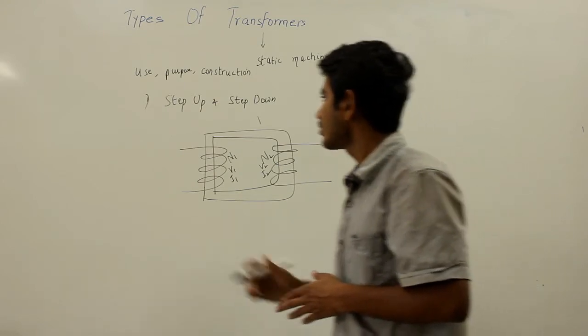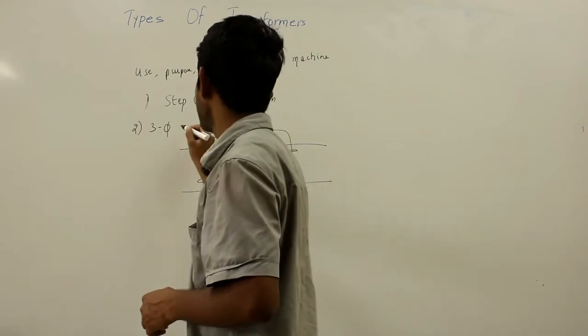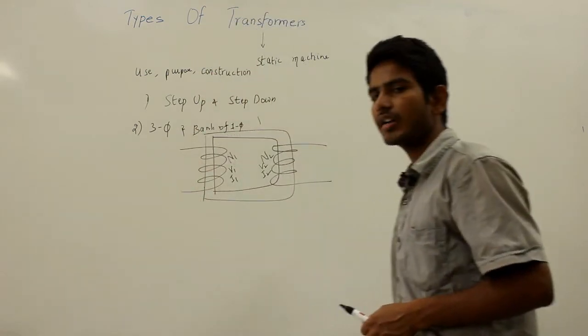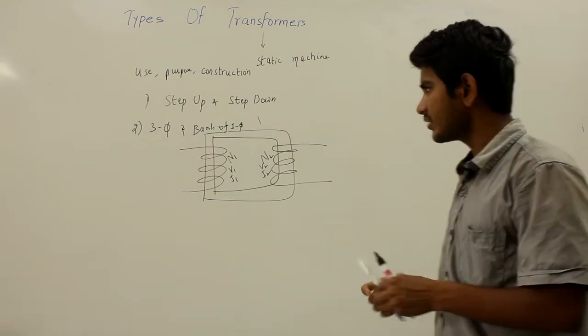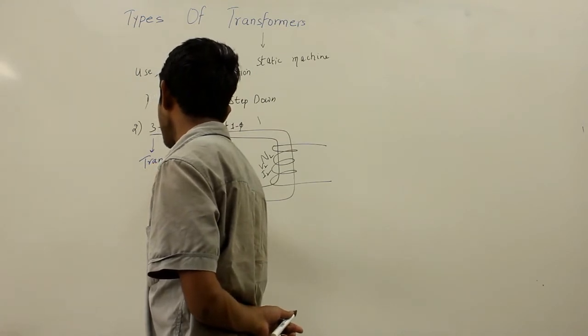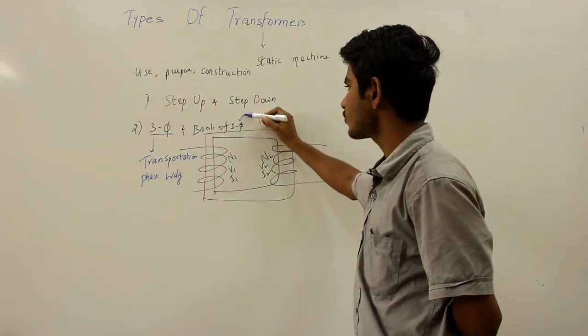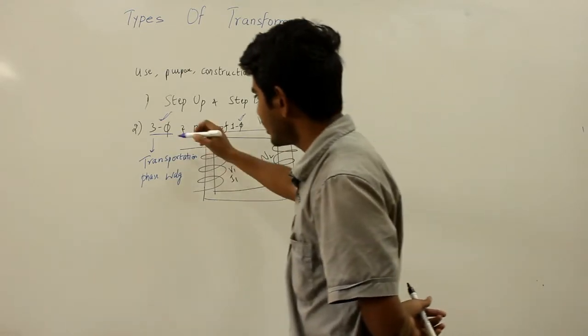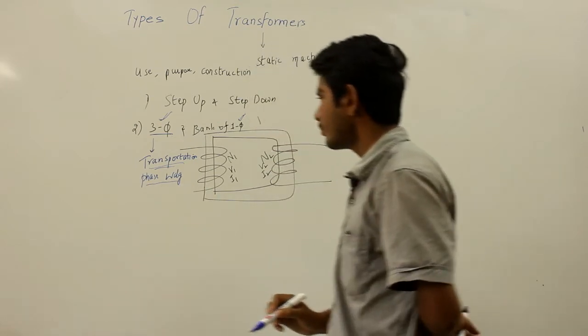The second type is the three-phase transformer and a bank of single-phase transformers. Three-phase transformers are used in three-phase power systems, but a three-phase transformer finds some difficulty in transportation and must be removed from service entirely if any of the phase windings breaks down. Where size matters, you can go for a bank of single-phase transformers.